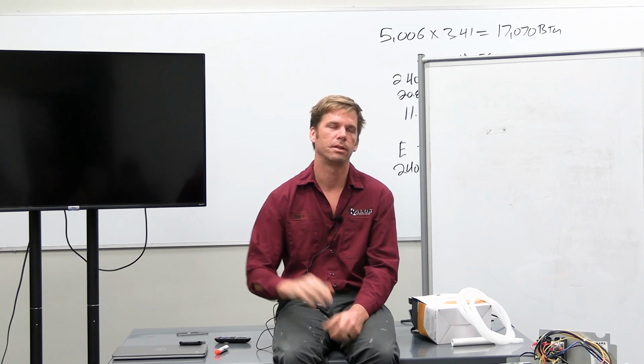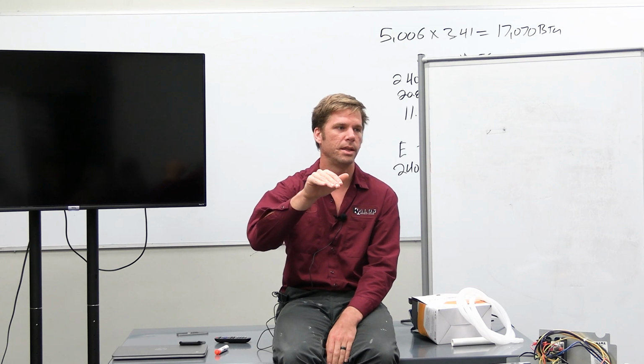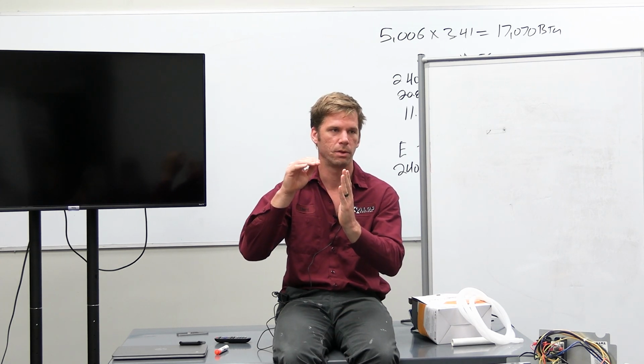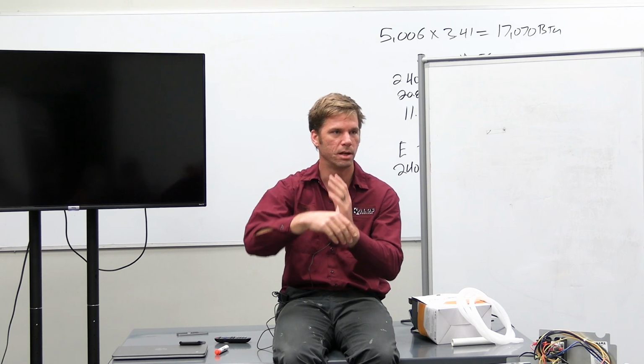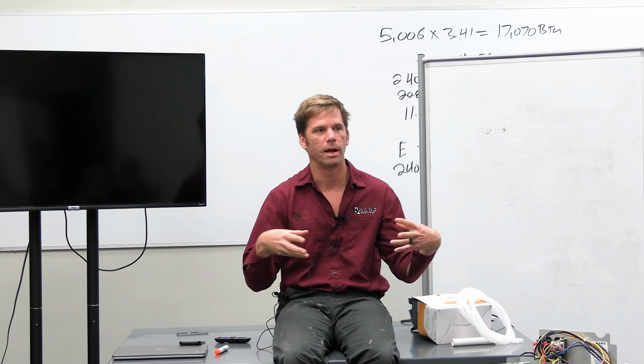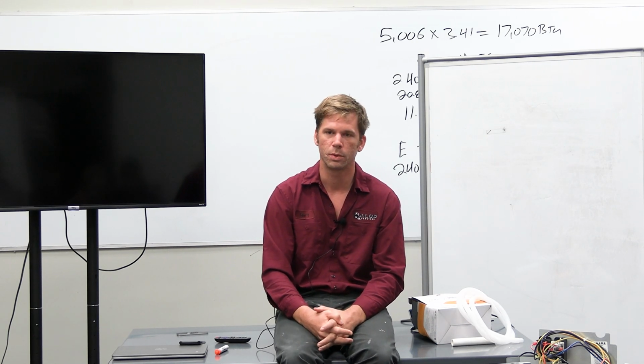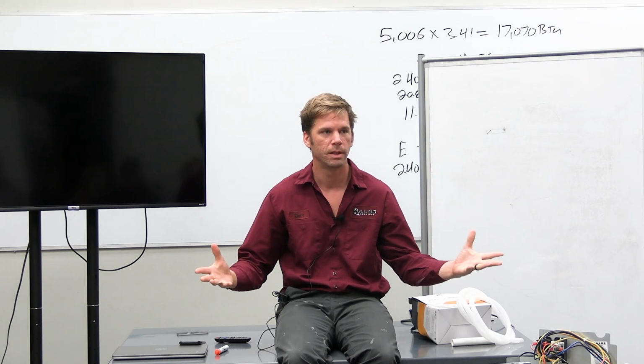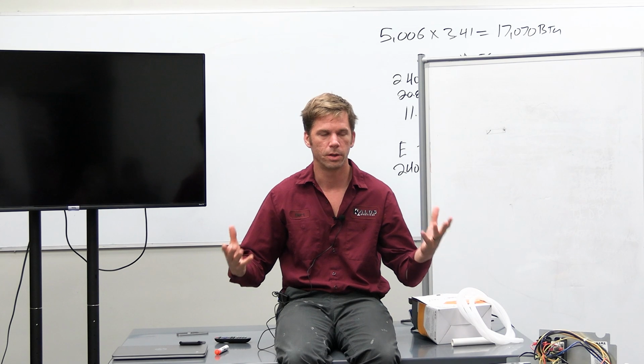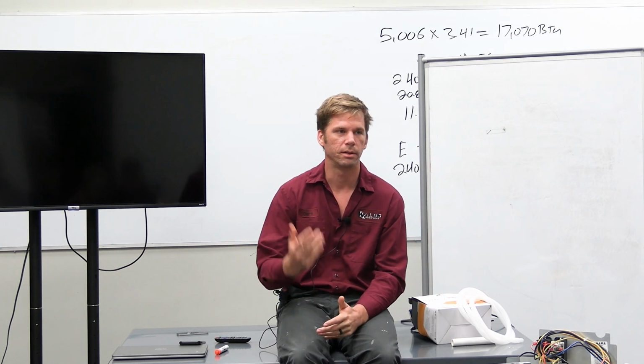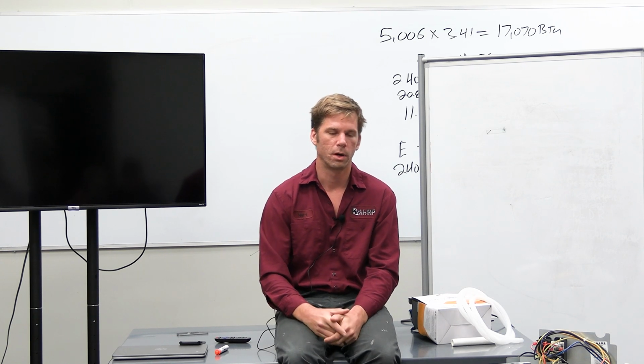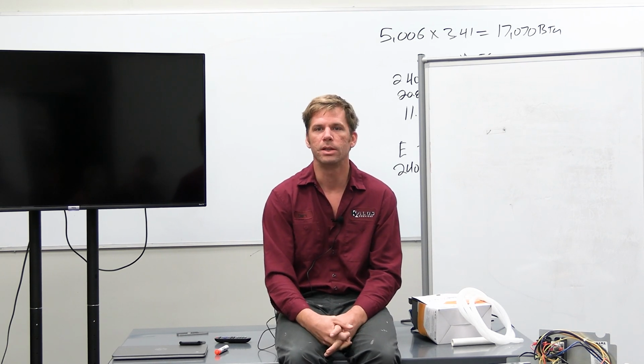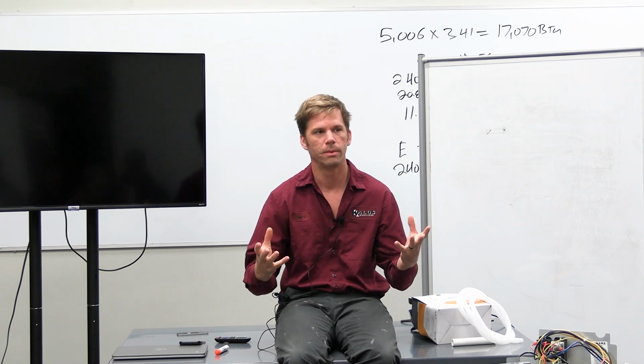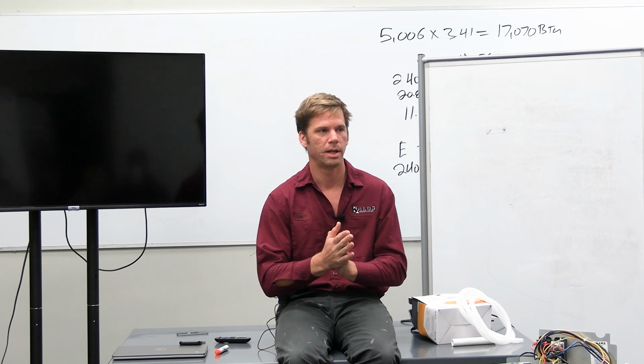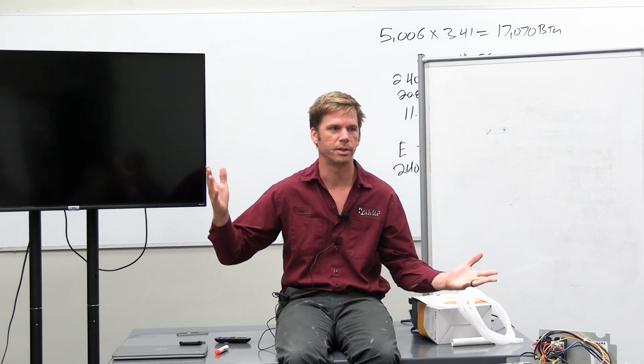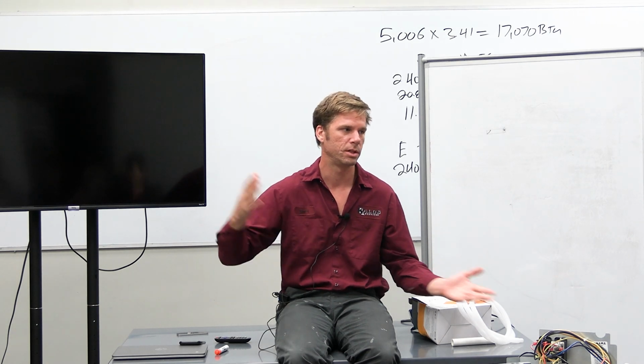Basically the sensor sends current from the board down the sensor, and then if there's flame, now we have a path for electricity flow through the flame into the heater and connect to the heater ground. So every once in a while you have issues where your whole heater bottom is rusted out, and there's not a good grounding location on the heater. Maybe somebody didn't ground the heater properly, or where the ground wire comes in, it's really corroded, and you have to find a way to ground your heater well in order for that flame sensor to have its opposite end of the electricity from the board to flow through, the potential difference needed.